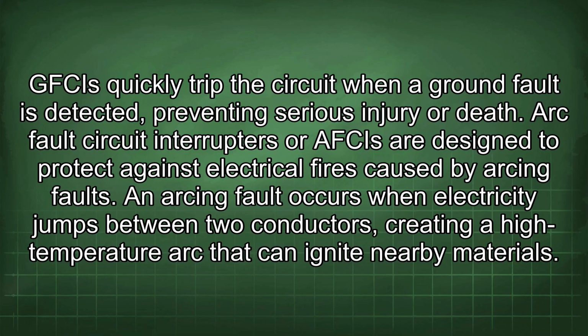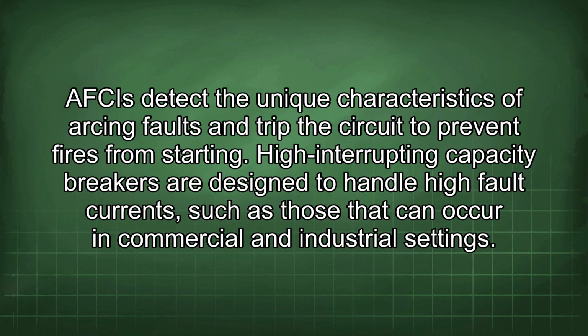Arc fault circuit interrupters or AFCIs are designed to protect against electrical fires caused by arcing faults. An arcing fault occurs when electricity jumps between two conductors, creating a high-temperature arc that can ignite nearby materials. AFCIs detect the unique characteristics of arcing faults and trip the circuit to prevent fires from starting.